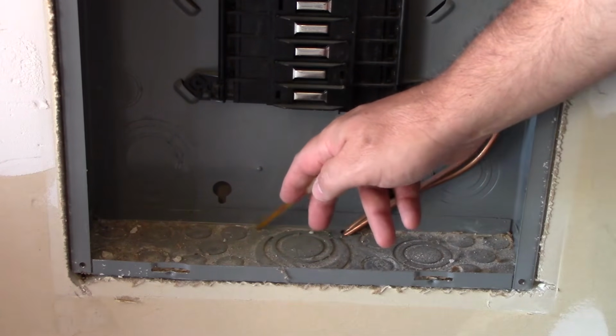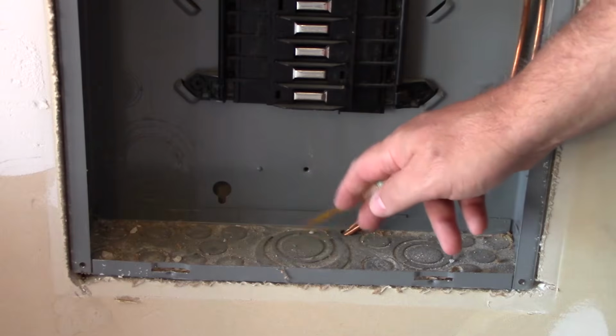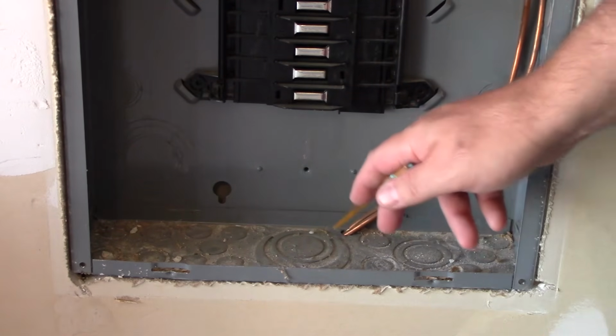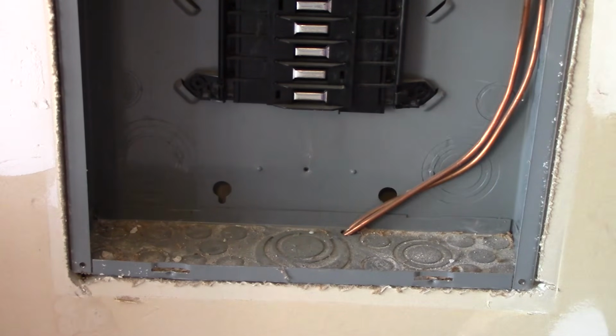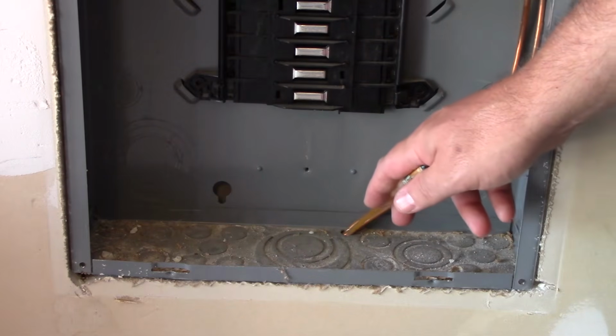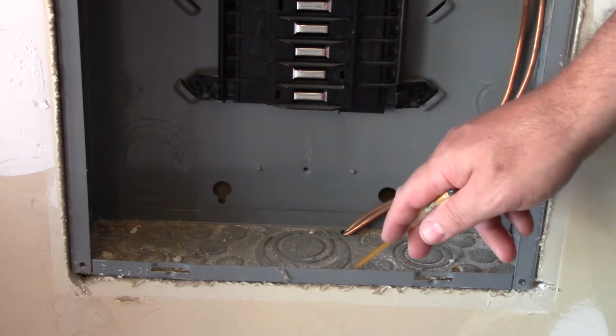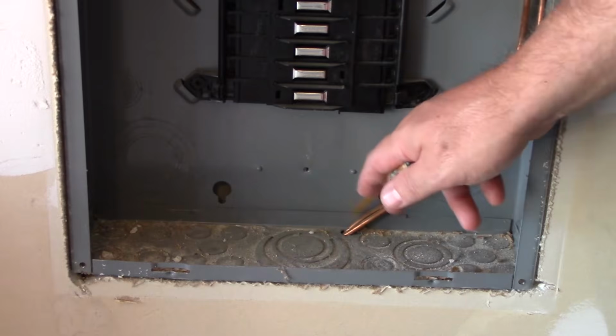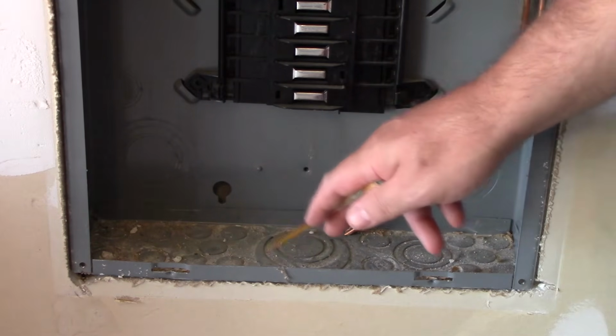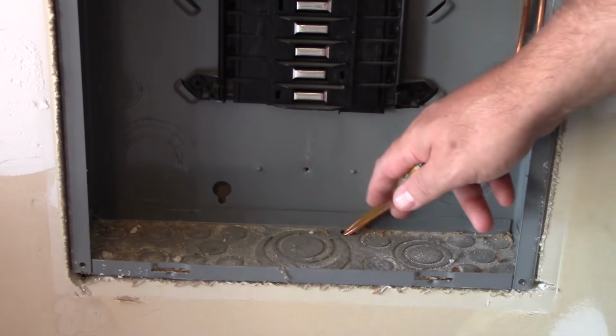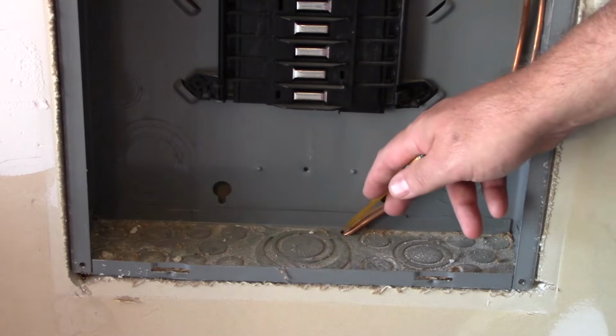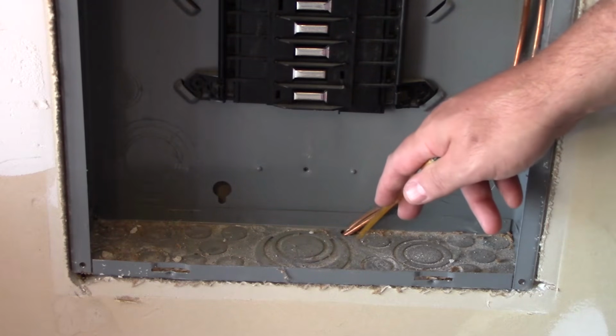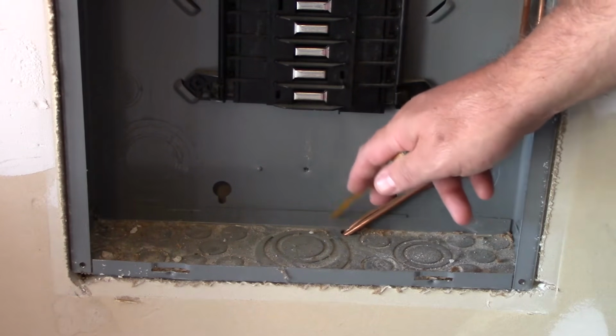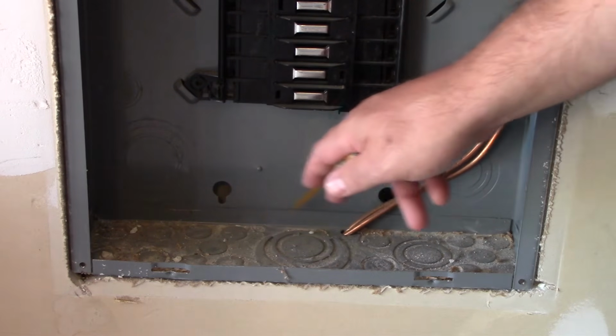This opening here, these little knockouts that are on either side of the main knockout, are designed to bring the grounding electrode conductors through. In this case, they brought two of them through the one opening. As a home inspector, I'm not too awfully concerned with that. They have two of them here, so they could have come through this one as well. But they didn't. They brought two of them, and it doesn't look like any damage on here. You kind of look at it. And so that's what this is designed for. And there's one on either side.